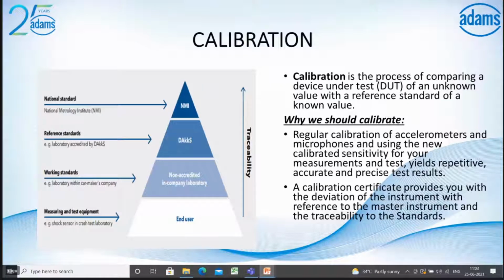Before getting into the subject, I just want to give you a small introduction about what calibration is and why calibration is so important. Calibration is a process of comparing an unknown value of a DUT with a known value of a reference standard. Why is calibration so important? It is for taking precise measurements with a well-known measurement uncertainty, with results that are comparable by the same standard, and for guaranteeing legal security, as the measurement results can be traced to the respective national standards.